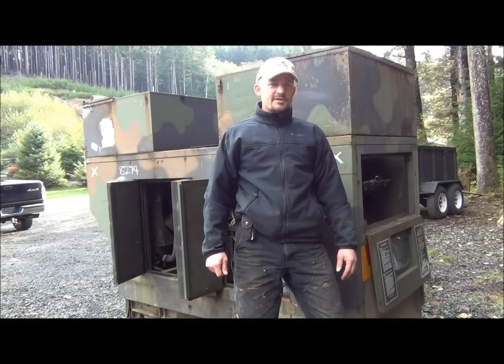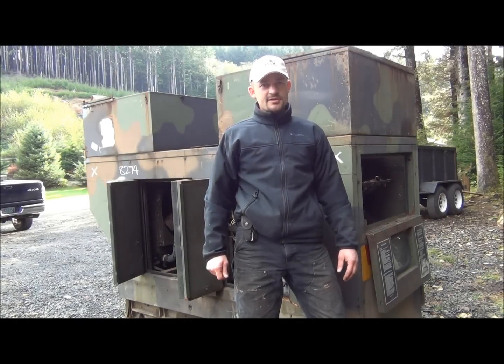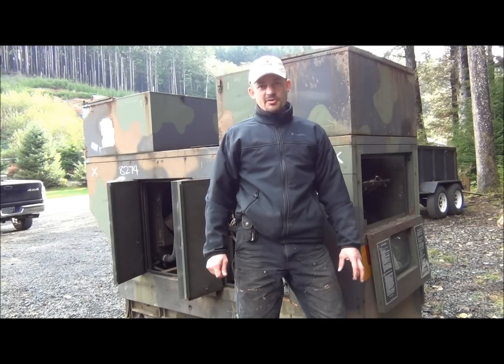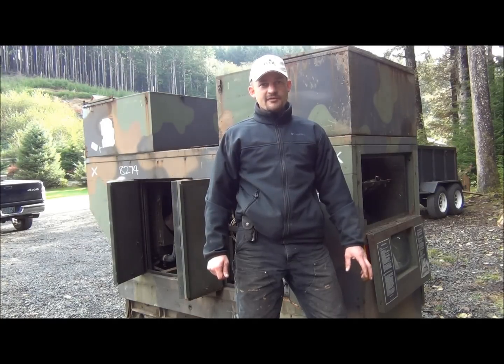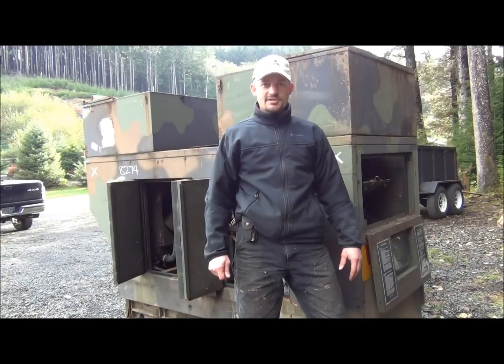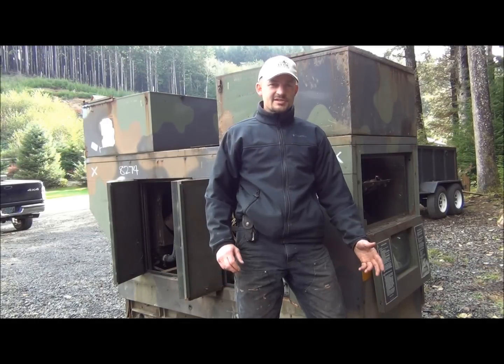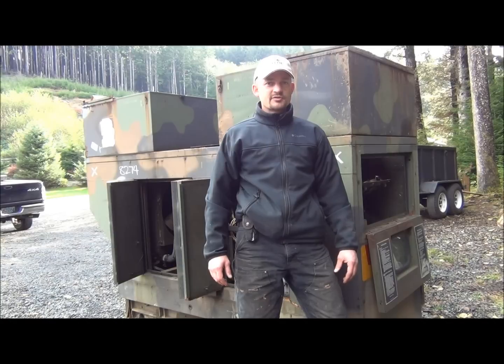Alright, the way that these frequency meters work on these MEP generators is that they use what's called a frequency transducer, and that provides a DC output that's proportional to the frequency input. Now, I've seen a few that are adjustable, so if they're off like this one is, you can actually adjust the bias on them and bring the frequency meter back into range. And I've also seen other ones that are a matched set, and you have to replace the frequency meter and the transducer at the same time.